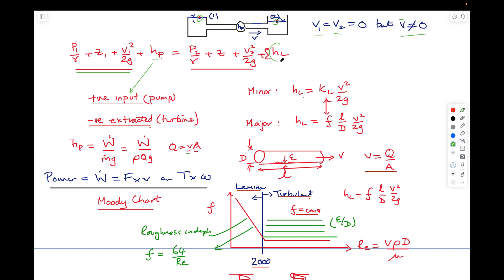Head losses fall into two categories. One is for bends and elbows, expressed as a loss coefficient times the velocity head. For major losses — pipe losses along the length of a pipe — also in units of length, they are a function of the velocity head, how long the pipe is relative to its diameter (L/D), and a friction factor.